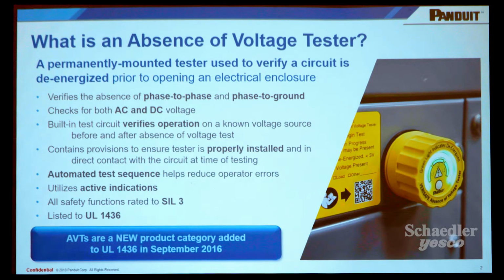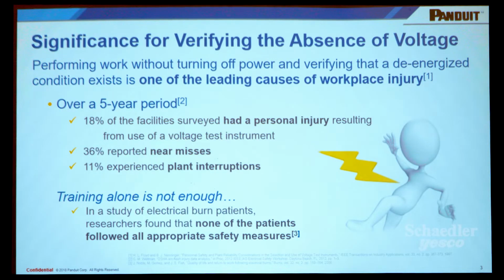So what is an AVT, or absence of voltage tester? Basically, it's a permanently mounted test system that indicates whether a panel is safe to enter. So it ties into the line or load side of the electrical system, typically in a control panel, MCC, or other enclosure, and when activated, it will tell you that the system's de-energized and the panel is safe to enter and service.